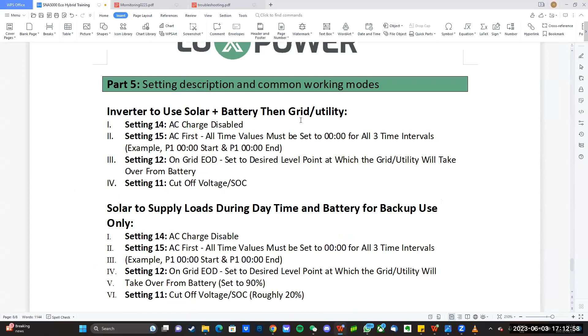If you want to program the inverter to use solar plus battery, then utility or grid, follow this exact sequence: program setting 14, then 15, then 12, then 11. For 12 and 11, the order matters because 11 is limited to the value of 12.